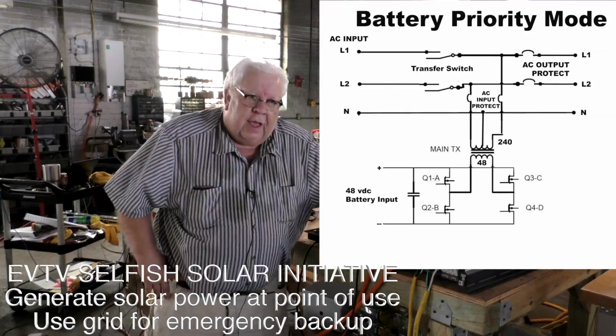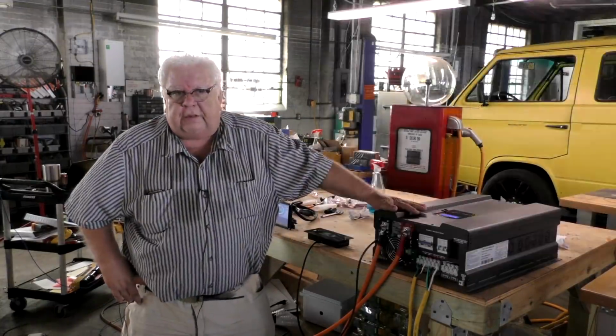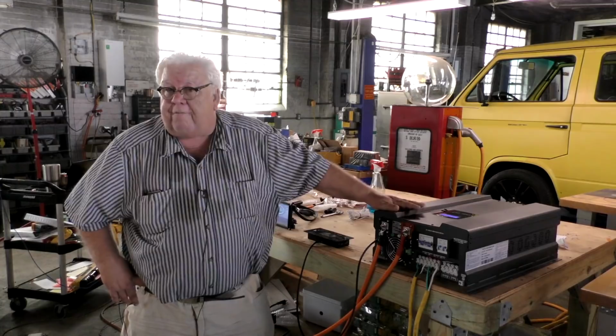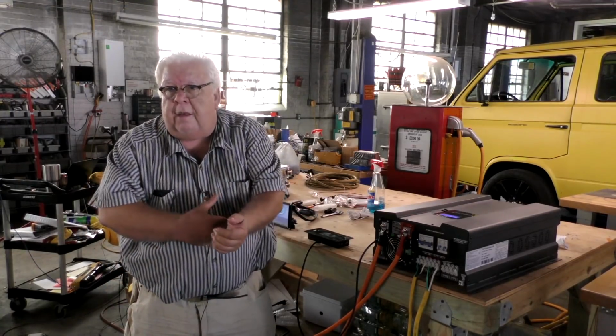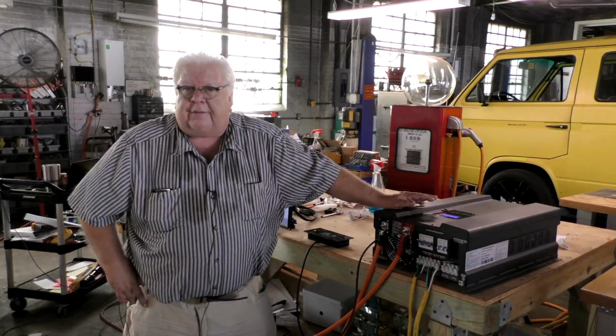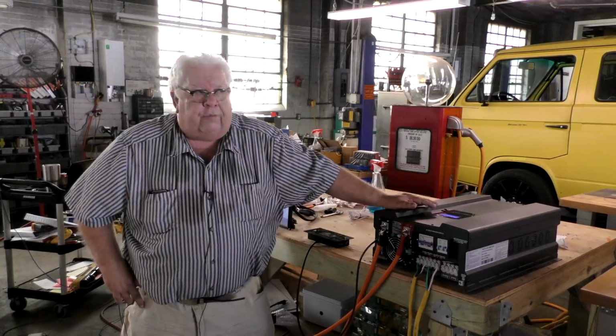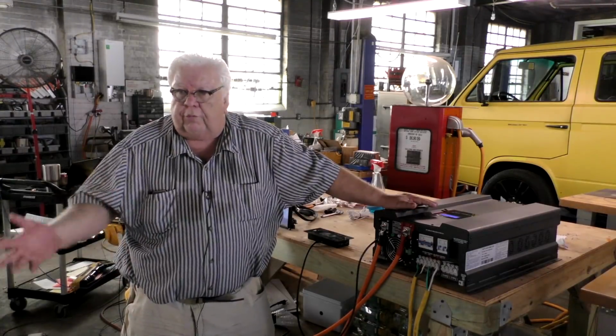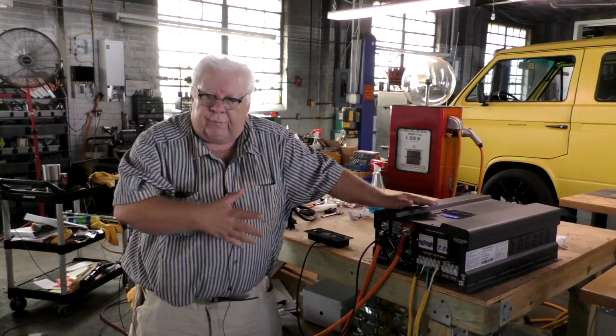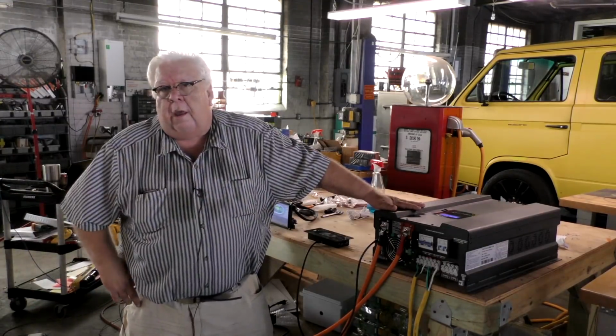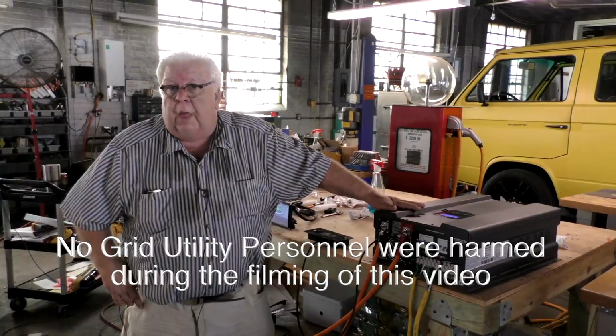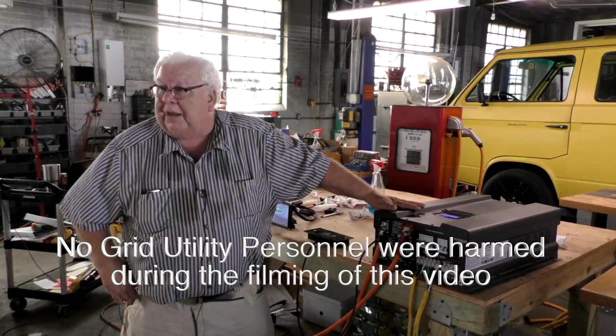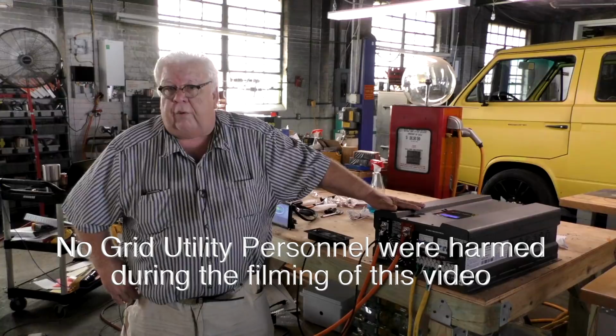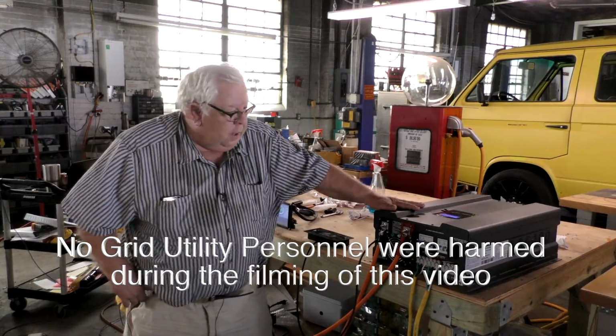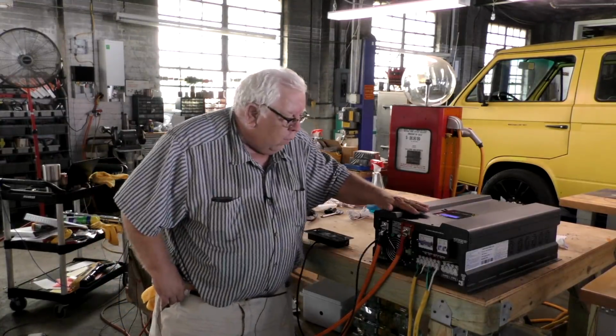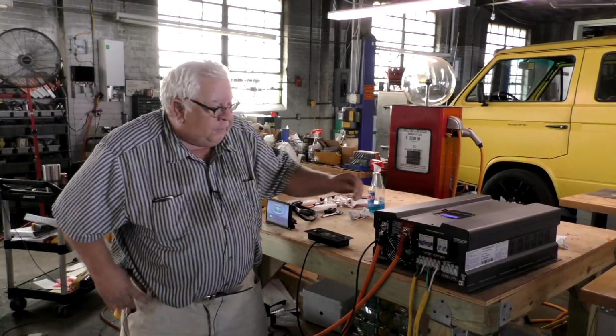So I like this. It's not UL listed or CE listed. It is UL 1741 compliant in that it has the transfer switch in it. There's no way, if you lose the grid, to ever take power from this and put it out the grid. And so no utility maintenance people were harmed in the filming of this video. And so this is our 12 kilowatt inverter.